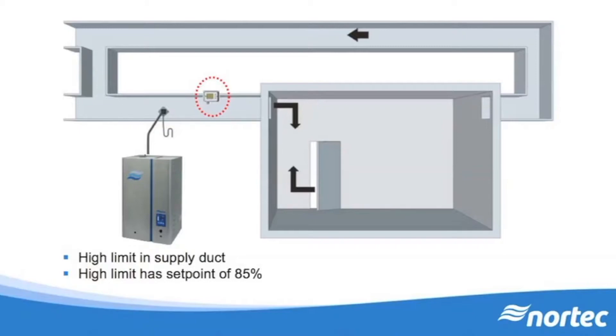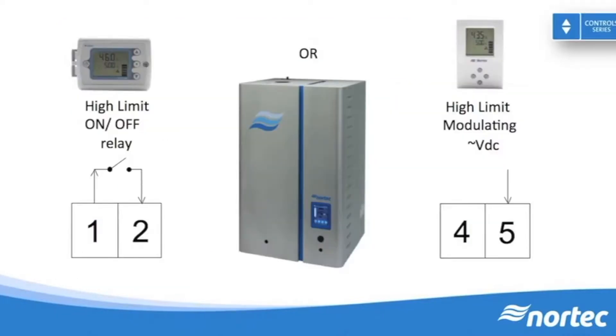A high limit will be placed in the supply duct downwind from the distribution and will have a high set point of 85%, when contrasted to a room controller that will be placed in the room and will have a required space set point of 40–60%. Again, the high limit humidistat can also be one of two types: on-off or modulating.